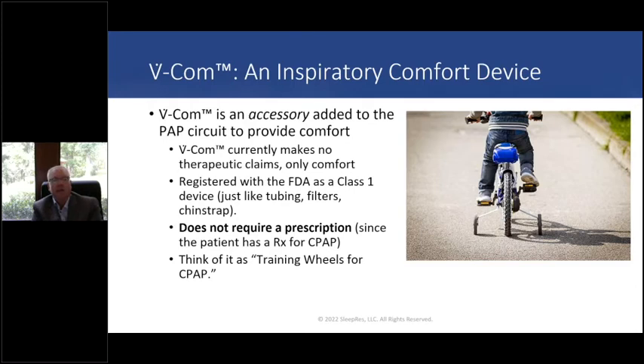VCOM currently makes no therapeutic claims, only comfort currently. That will likely be coming. It's registered as an FDA class one device, just like tubing, filters, and chin strap. Does not require a prescription, since the patient has a prescription for CPAP and its only indication is for CPAP or non-invasive ventilation.